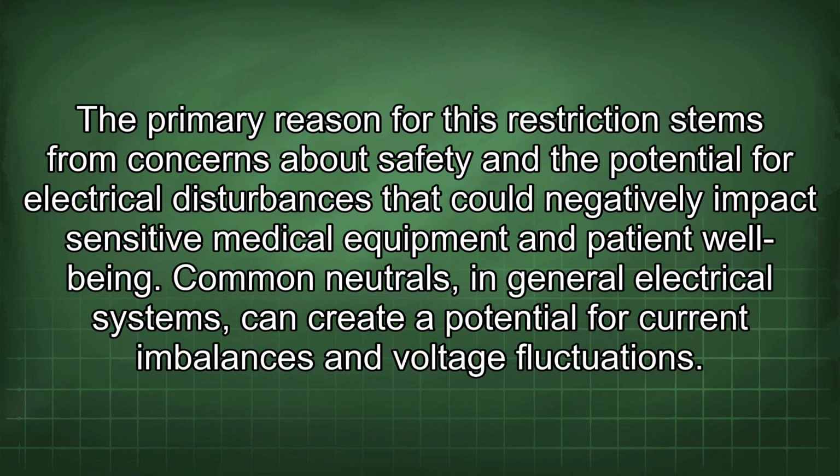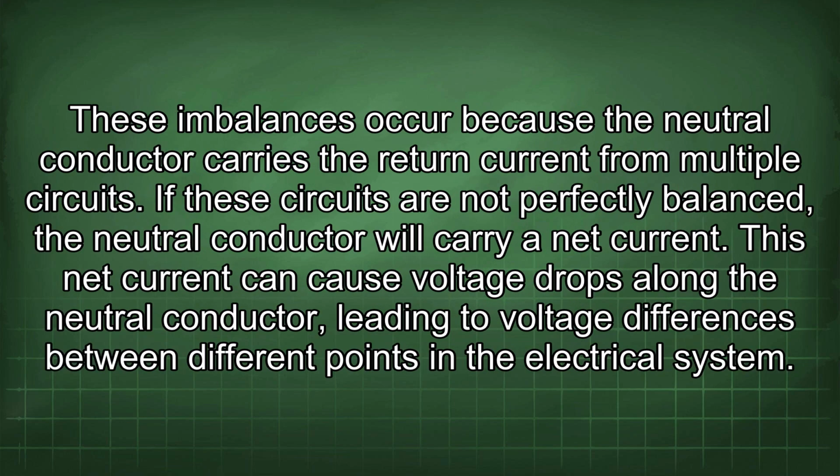The primary reason for this restriction stems from concerns about safety and the potential for electrical disturbances that could negatively impact sensitive medical equipment and patient well-being. Common neutrals in general electrical systems can create a potential for current imbalances and voltage fluctuations. These imbalances occur because the neutral conductor carries the return current from multiple circuits. If these circuits are not perfectly balanced, the neutral conductor will carry a net current.